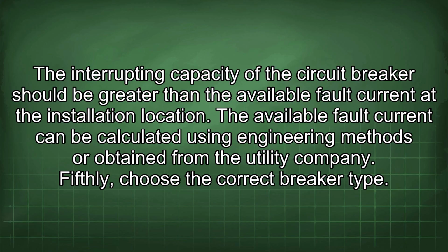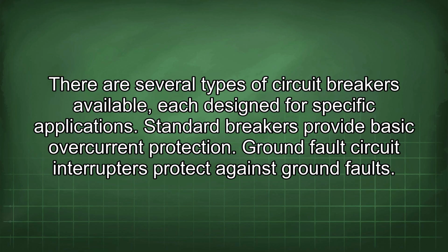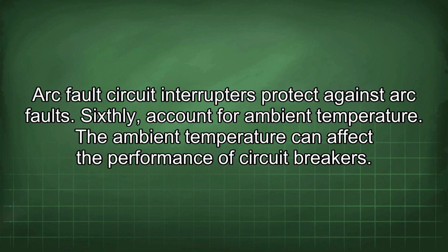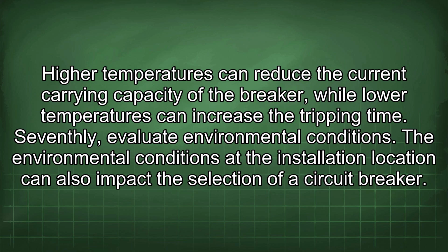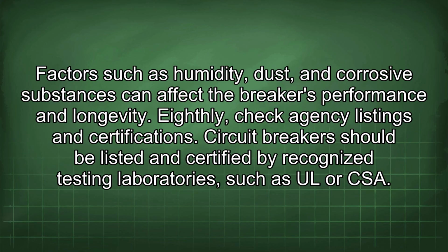Fifthly, choose the correct breaker type. There are several types of circuit breakers available, each designed for specific applications. Standard breakers provide basic overcurrent protection. Ground fault circuit interrupters protect against ground faults. Arc fault circuit interrupters protect against arc faults. Sixthly, account for ambient temperature. The ambient temperature can affect the performance of circuit breakers. Higher temperatures can reduce the current carrying capacity of the breaker, while lower temperatures can increase the tripping time. Seventhly, evaluate environmental conditions. The environmental conditions at the installation location can also impact the selection of a circuit breaker. Factors such as humidity, dust, and corrosive substances can affect the breaker's performance and longevity.